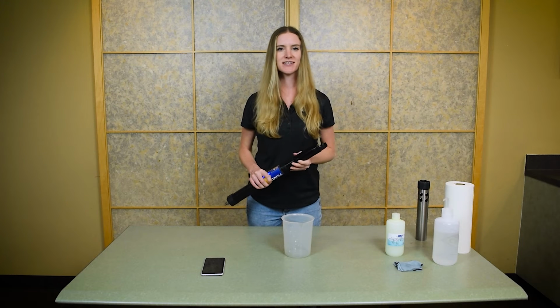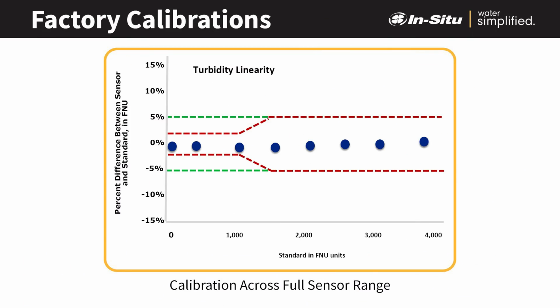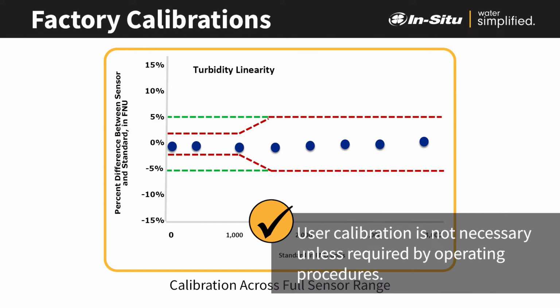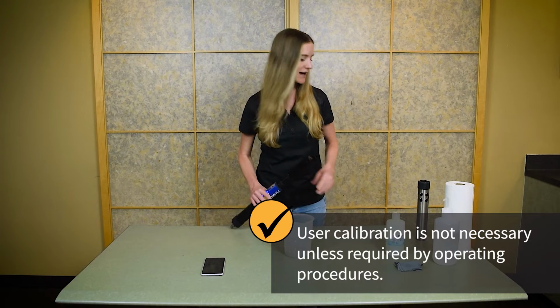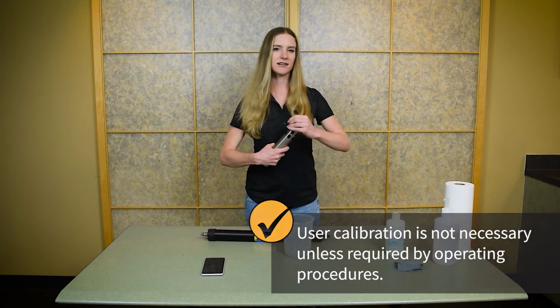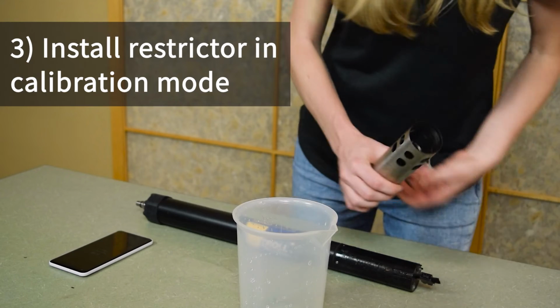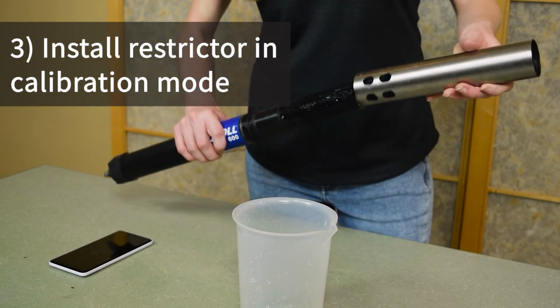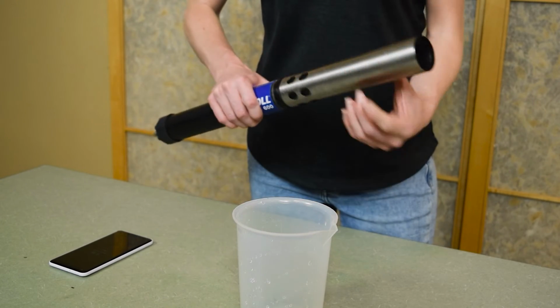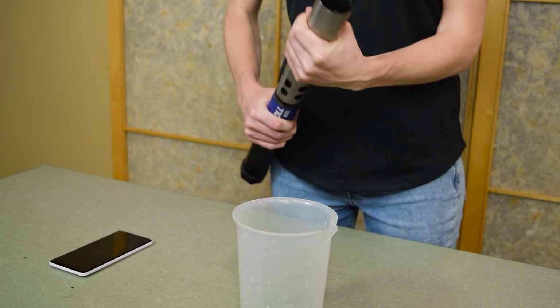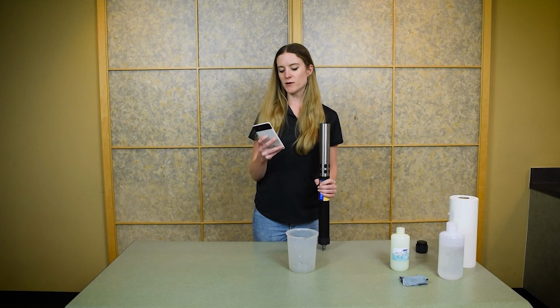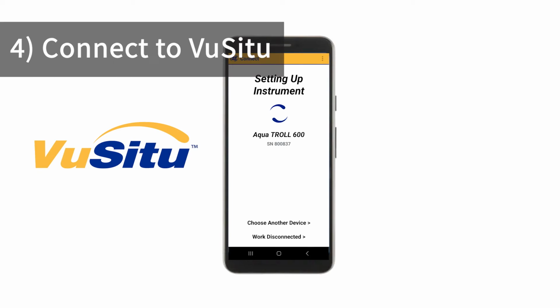Turbidity sensors are rigorously tested across their full range, and they don't tend to drift over time. This means there's no need for you to calibrate unless you have procedures that require it. If you would like to calibrate your sensor, install the restrictor in calibration mode with the holes away from the center of the instrument. Open the VuSitu mobile app and connect to the instrument.